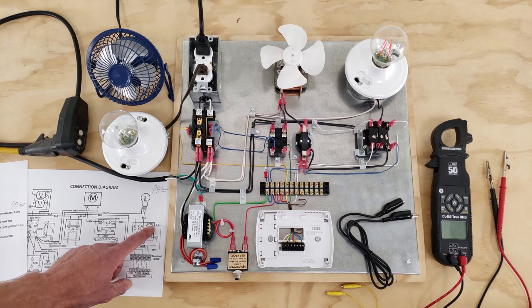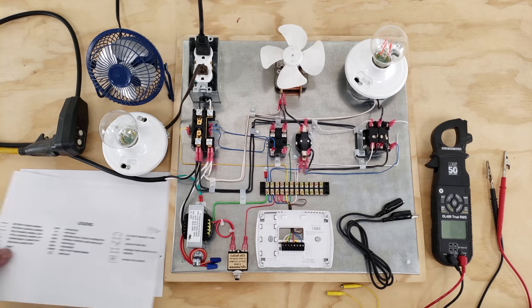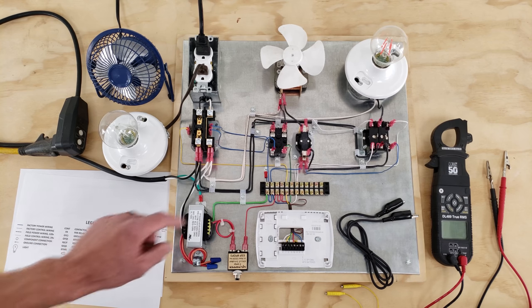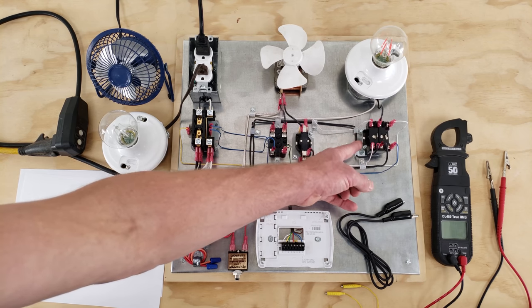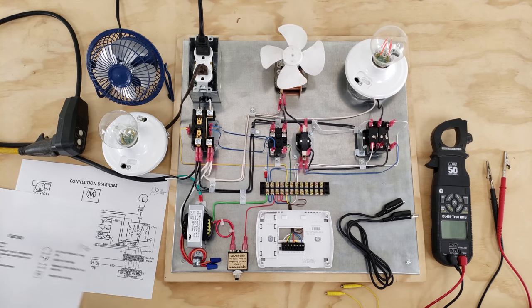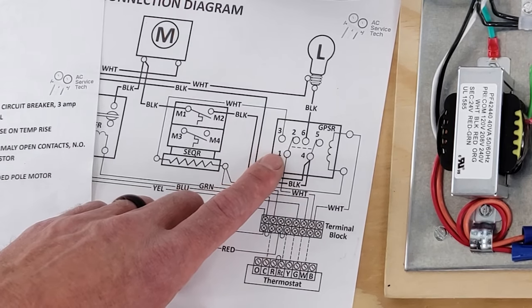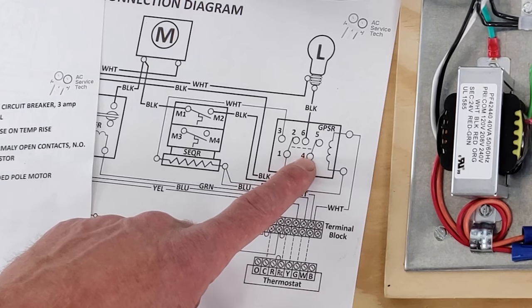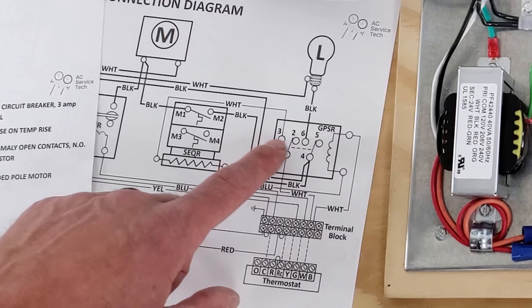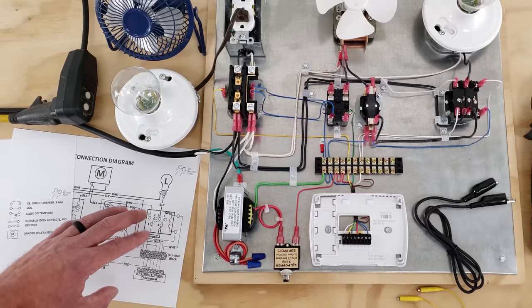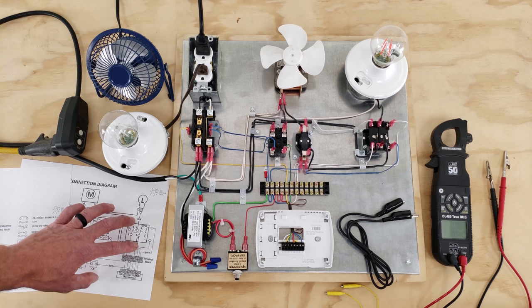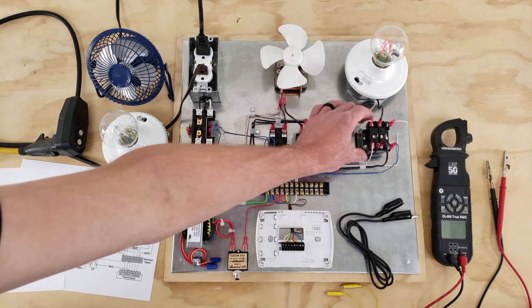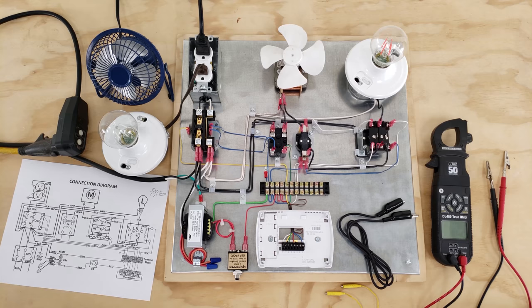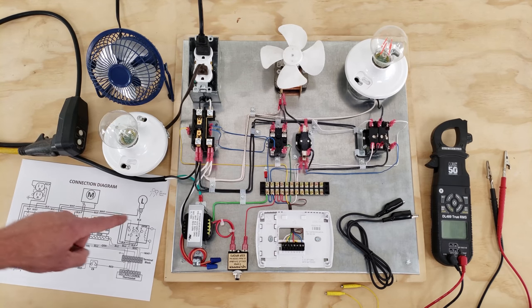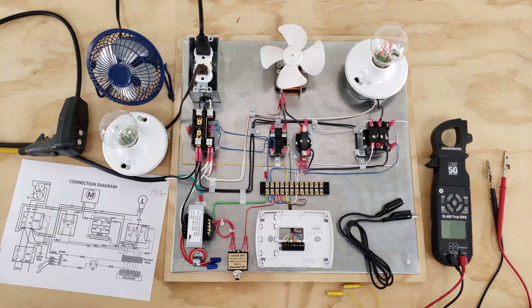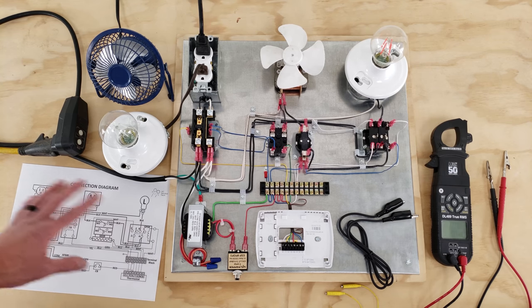Here, you have a GPSR. Well, what's that? You just go right over to your legend. GPSR, general purpose switching relay, that's right here. This is a DPDT relay. That means that it's double pole. There's one pole there and one pole there, and then it's double throw, so it can throw either way. And so we're actually controlling two circuits on the switching part of this relay right here. The simple little ones up at the top, we have our M, that's our motor, our light bulb right there. And so basically that's how you know which of the components are.